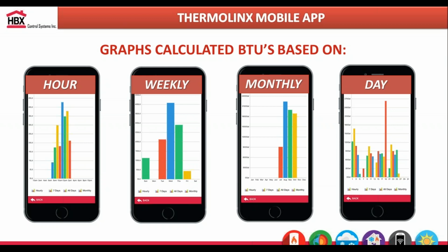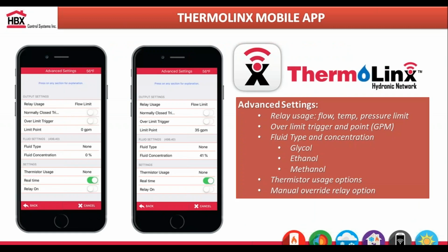If you ever get a big utility bill, you can justify that, hey, on these certain days I really had big spikes in flow and the amount of heat I was producing. Justify it through the HBX app, which again is free. You can also adjust your fluid type, so you can use this for glycol, ethanol, or methanol, depending on the application. You can enter your concentration, and it will calculate based on the concentration you're using in the app.